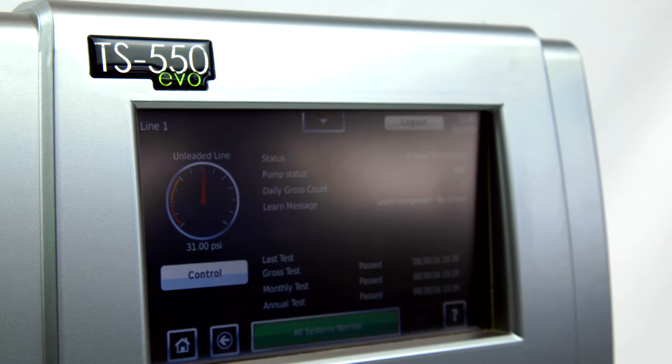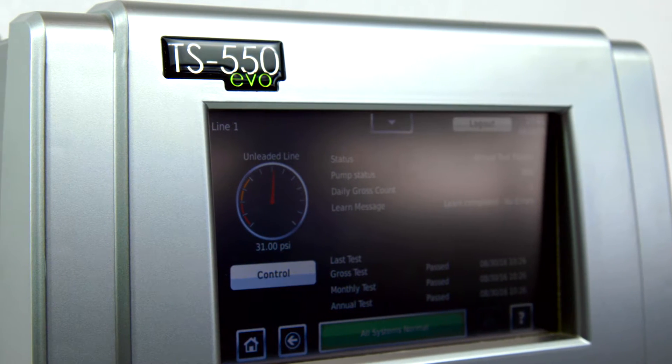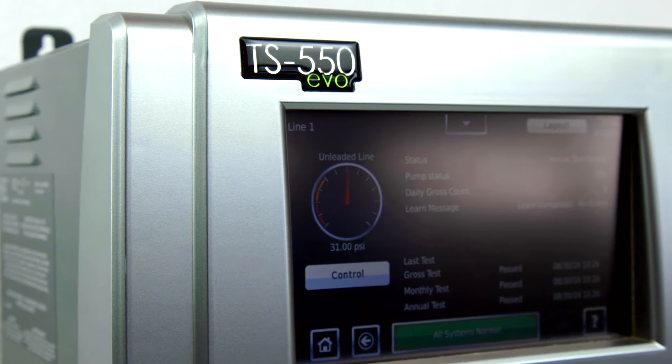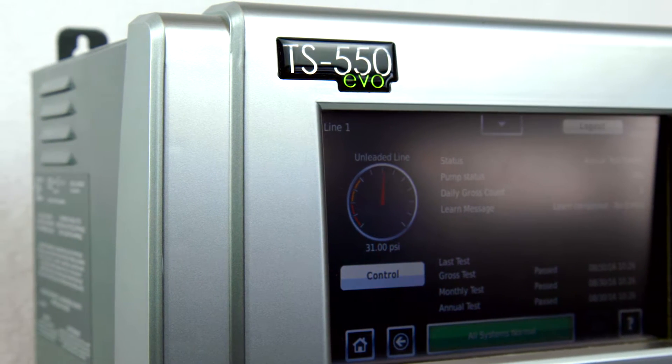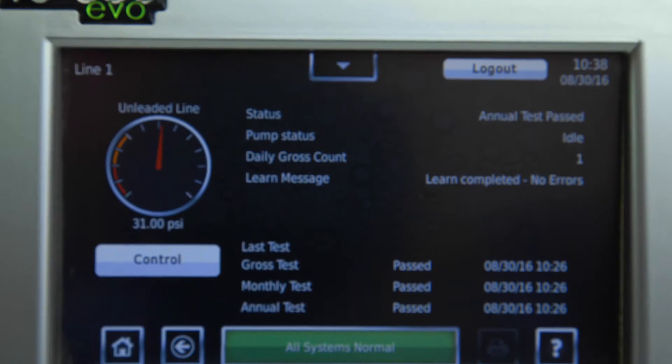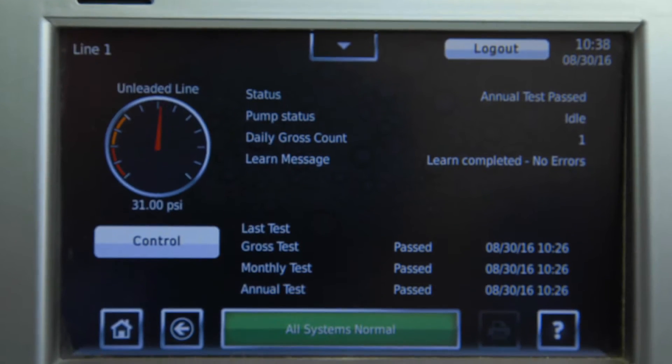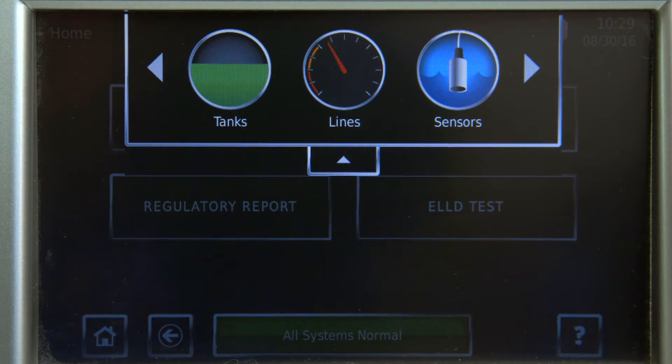Electronic line leak detection is a method of performing leak tests on your lines at a site to ensure those lines are not leaking. ELLD is an optional software package on the TS-550 EVO. Most people are familiar with statistical tank testing, but a unique feature that Franklin Fueling Systems has is statistical line leak detection.